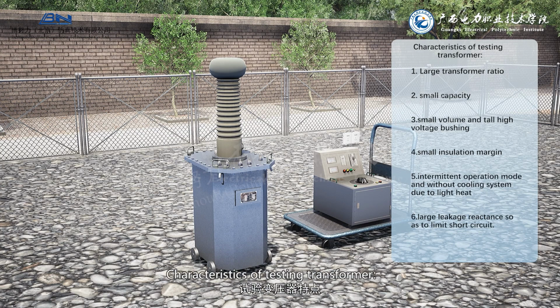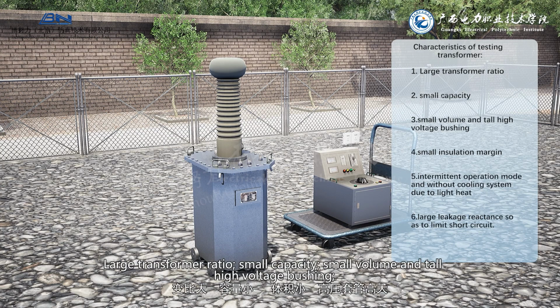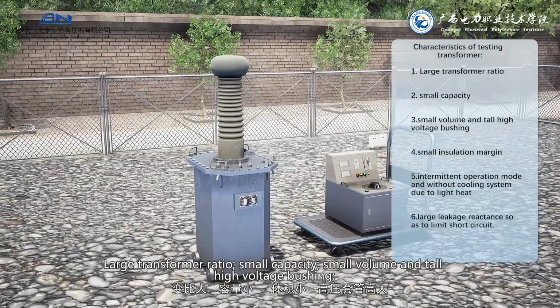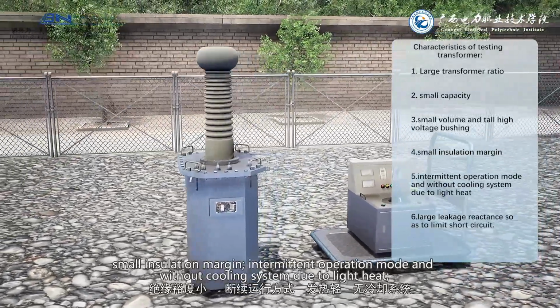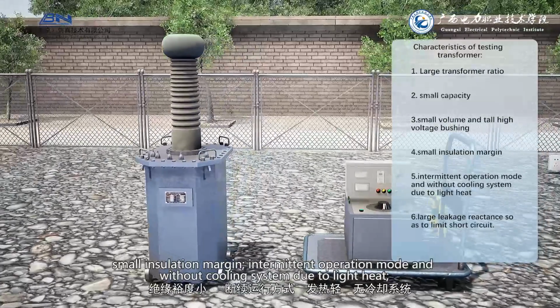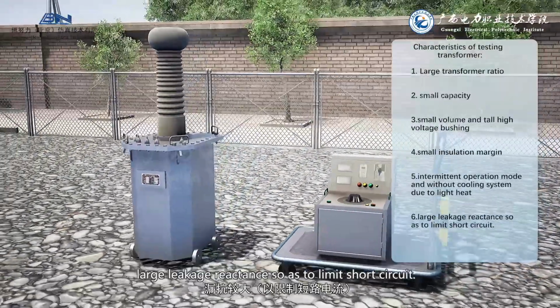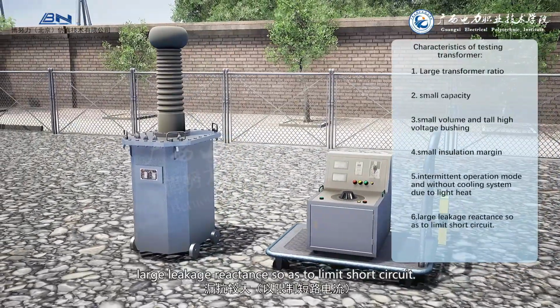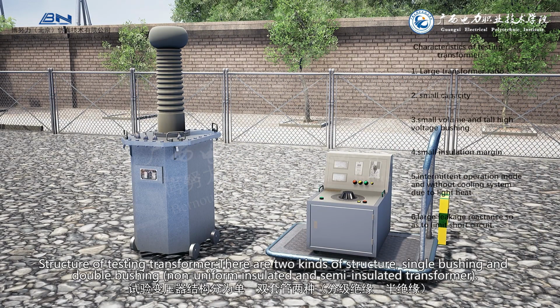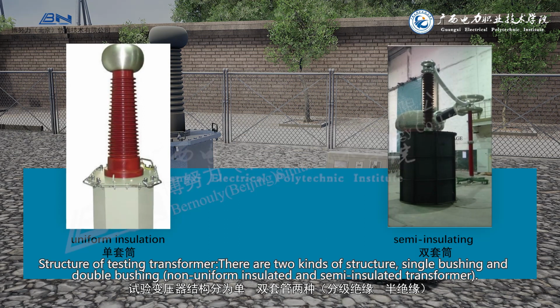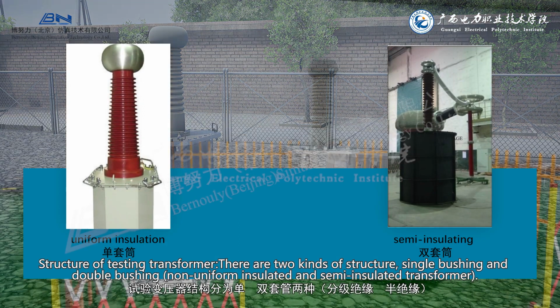Characteristics of testing transformer: large transformer ratio, small capacity, small volume and tall high voltage bushing, small insulation margin, intermittent operation mode, and no cooling system due to light heat, with large leakage reactance so as to limit short circuit. Structure of testing transformer: there are two kinds of structure: single bushing and double bushing, non-uniform insulated and semi-insulated transformer.